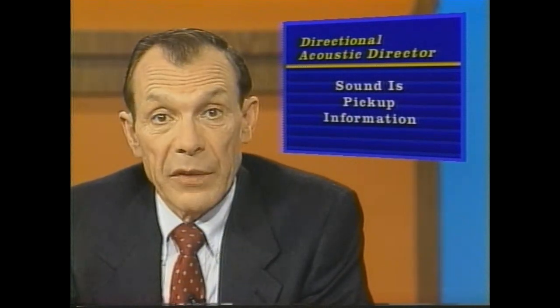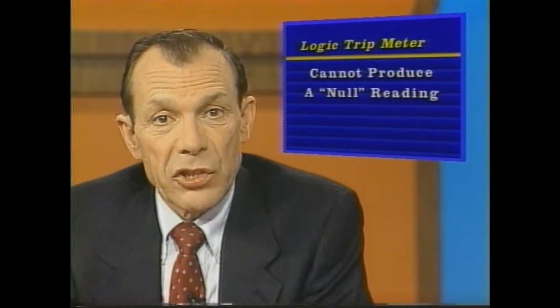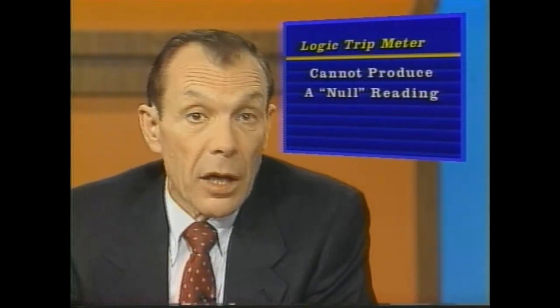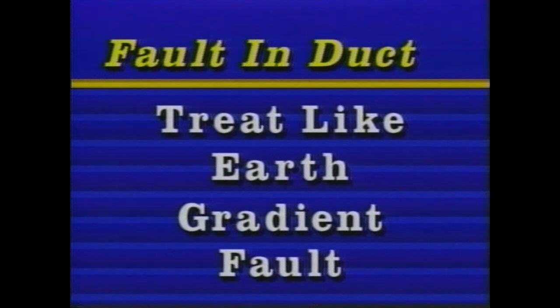Using the same method used in earth gradient fault locating, you can move the probes back and forth to zero in on the fault. The directional acoustic detector operates very similar to an earth gradient, but there are two major differences. The acoustic uses sound, not gradient currents, in its pickup information. And the logic trip meter must trip in one direction or the other. It cannot produce a null reading. Directional acoustics can help locate a fault in a duct. Place a microphone each side of the duct, then treat it like an earth gradient fault locate.